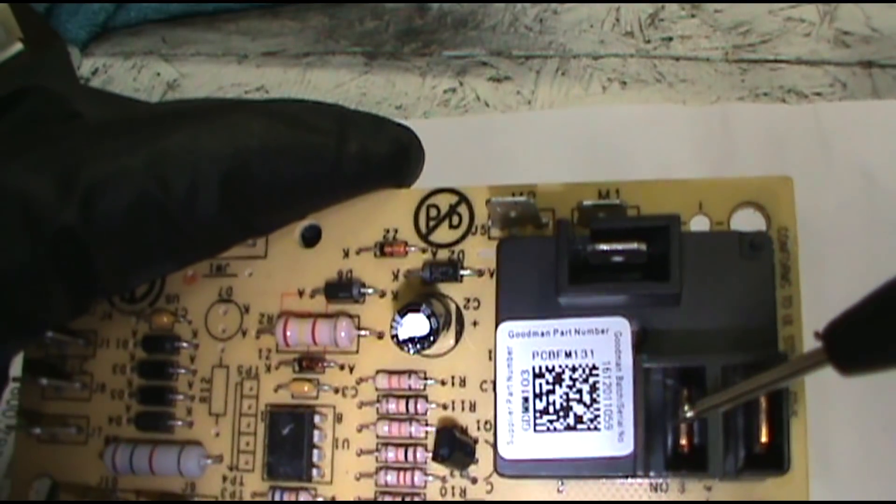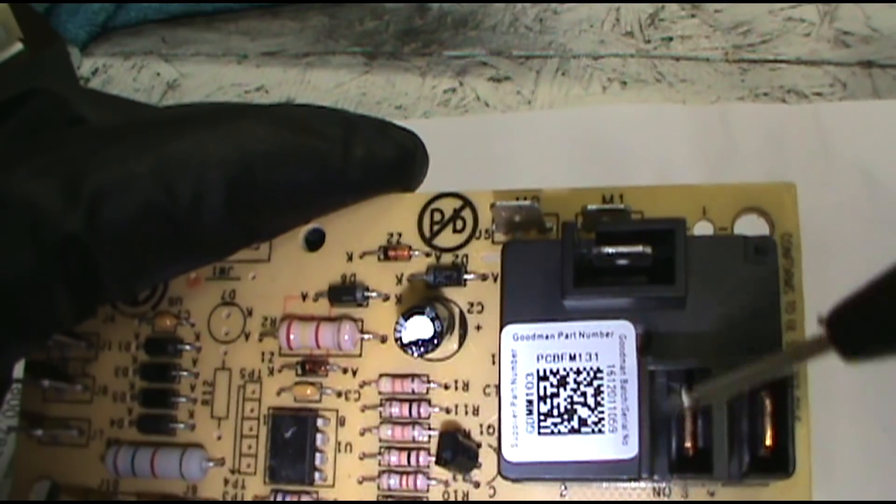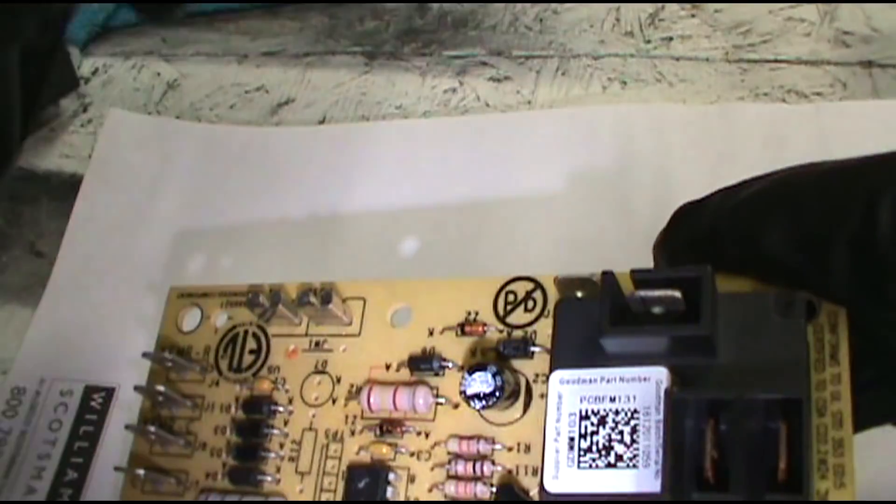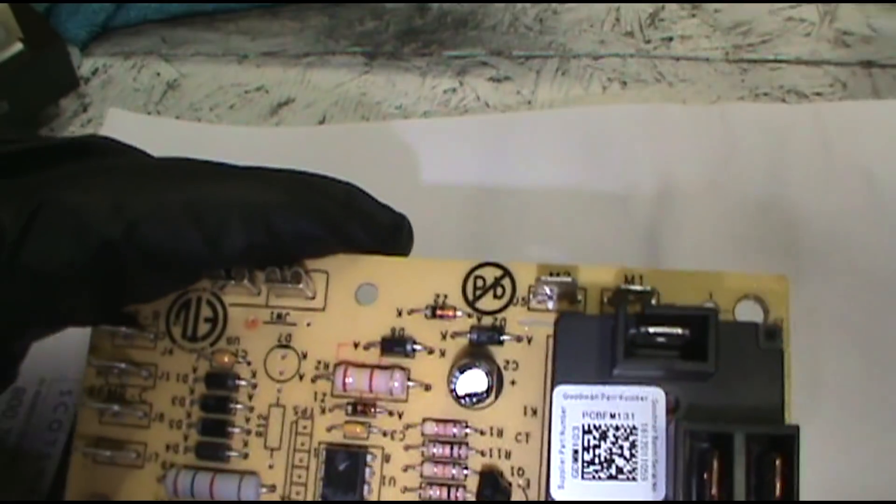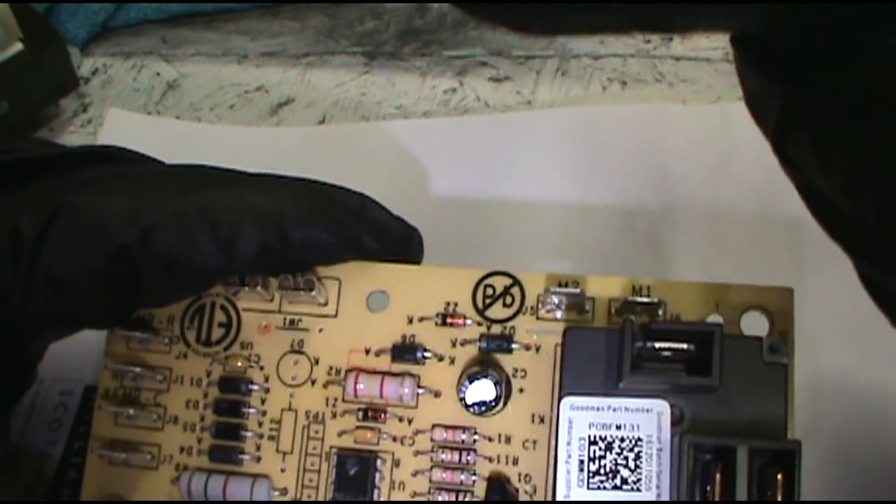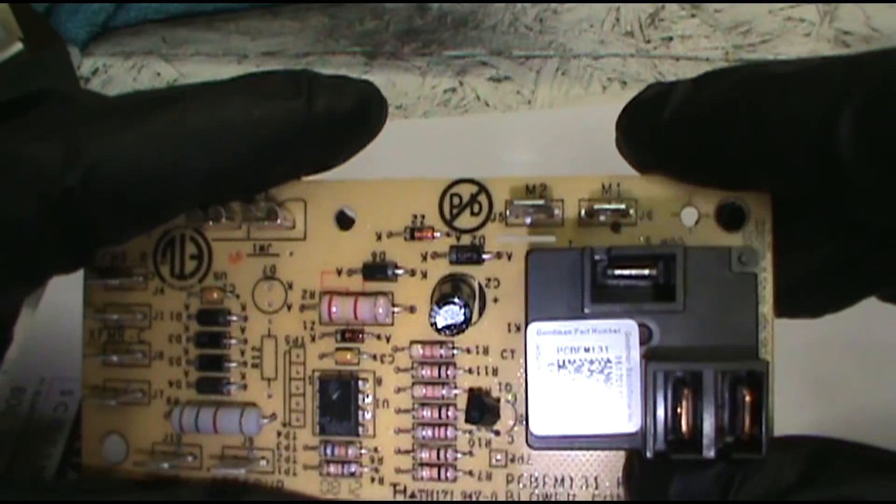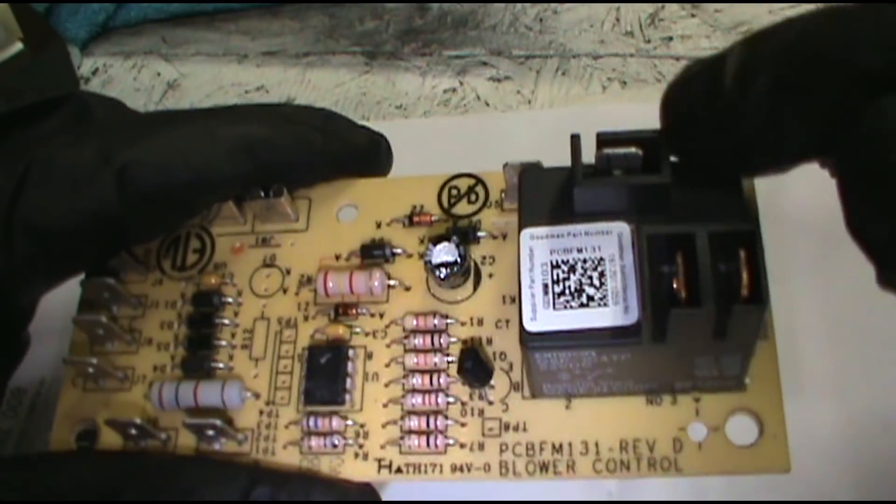Now if the switch gets stuck open and it won't close, then the fan won't come on at all. And I've also seen a guy, he pulled the common wire out and stuck it onto the lug of the power, the power lug for the air handler, and the fan came on. And that's how he troubleshooted this being bad.